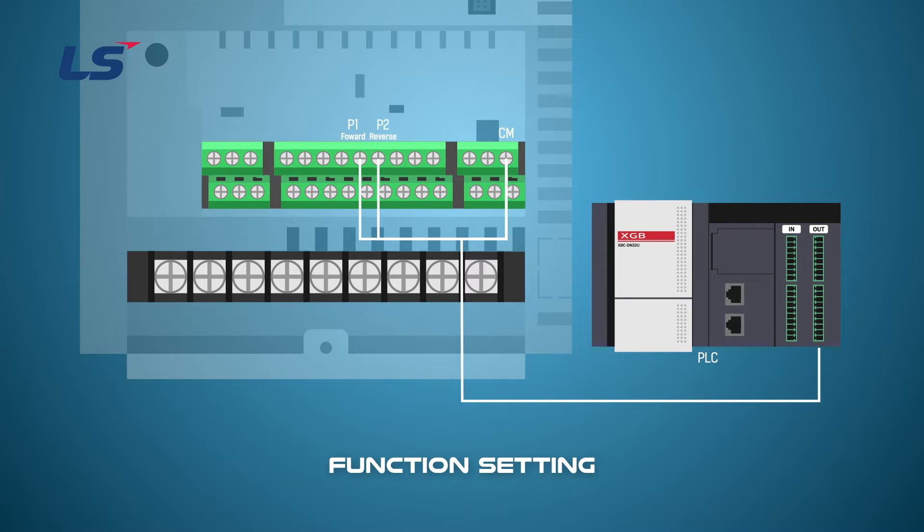Multi-step speed will be connected to P5 and P6. When the P5 terminal is activated, it becomes multi-step first stage. And when the P6 terminal operates, it becomes multi-step speed second step.